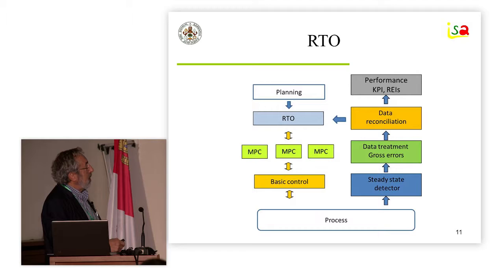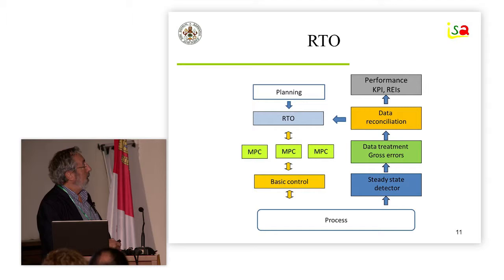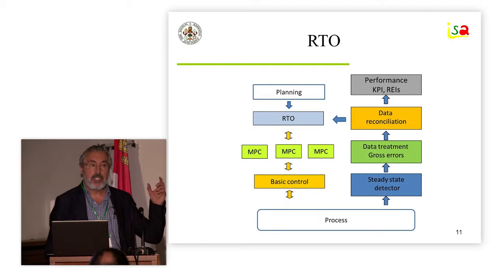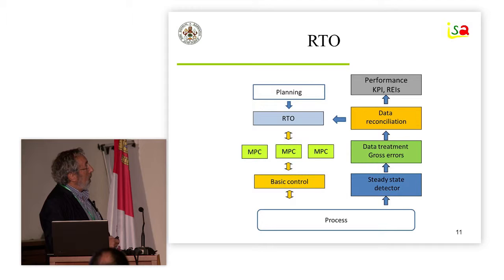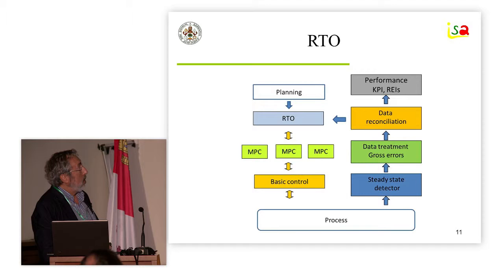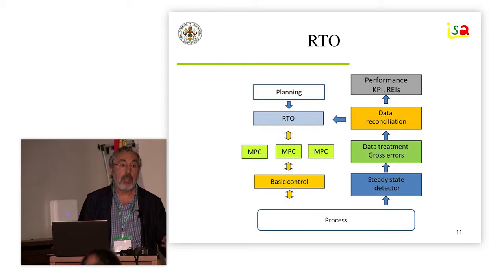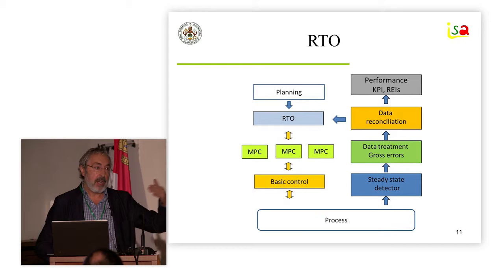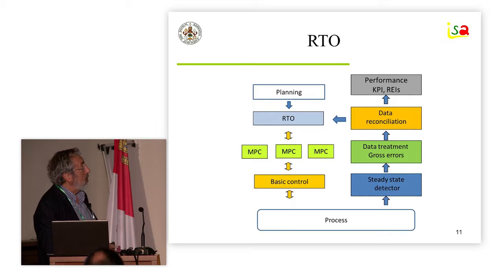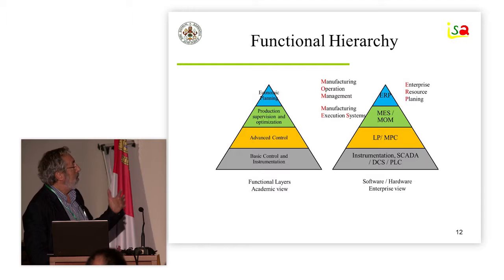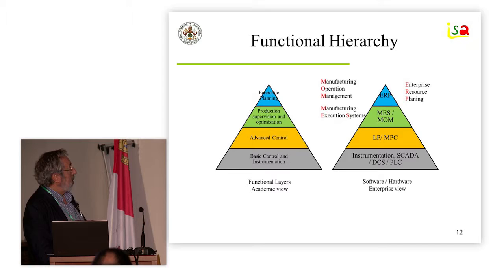In theory, RTO sets the set points of different MPCs for different parts, or directly goes to basic control. Your RTO depends on the planning level, and you interact a lot at this level. In order to know how well you are operating, you should compute some KPIs — key performance indicators — or resource efficiency indicators that give you an idea of how the plant is going. The purpose of the RTO is to maintain good values in these global indicators of the plant. This fits more or less into the typical pyramid of control structure.